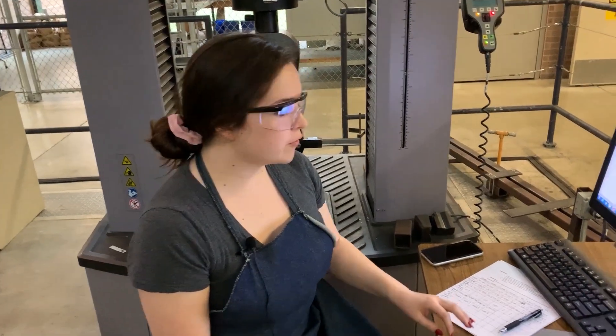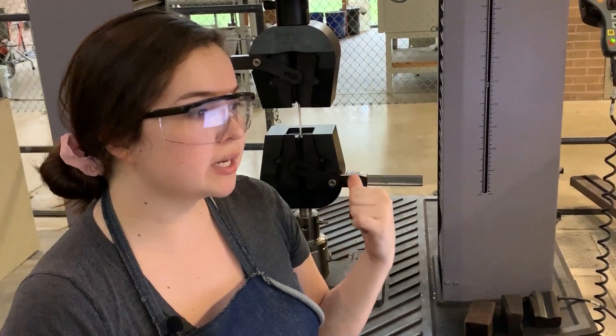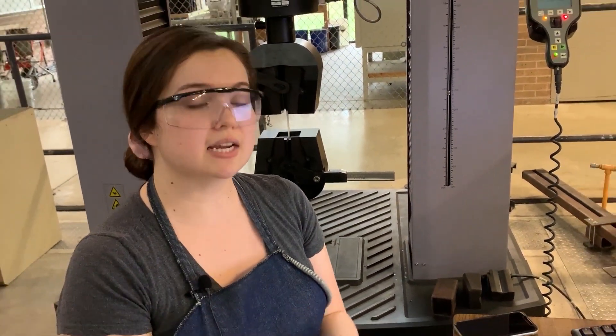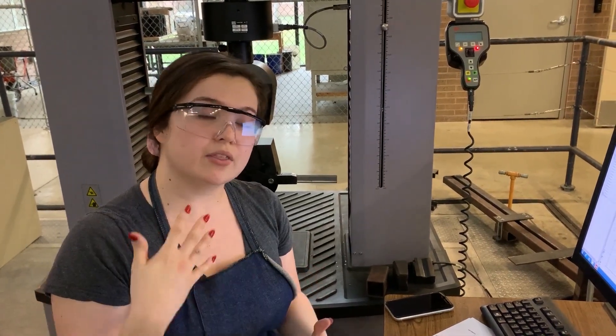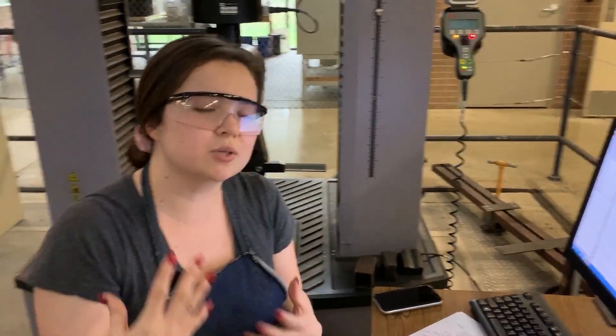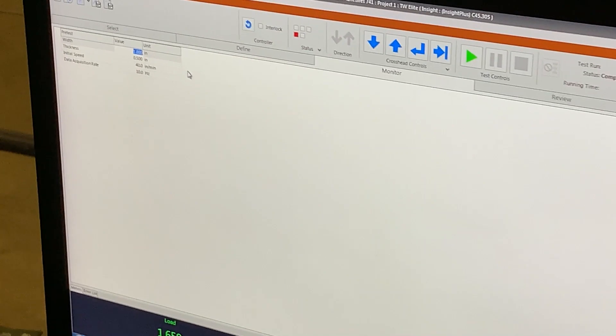Now we're going to be testing the different types of polymers at a test rate of two inches per minute. We're starting off with polypropylene, which is known to be a rubbery polymer, so there's a possibility it could take quite a while to reach full elongation. There have been cases where it fractures like a broom, and other cases where it won't even break and exceeds the elongation of the MTS itself. I'm going to input the data now — setting it to two inches per minute and zeroing out the load.